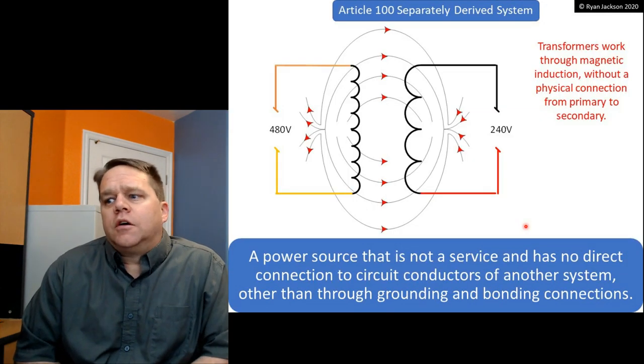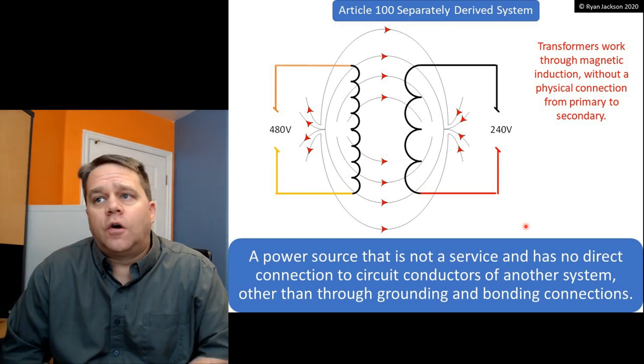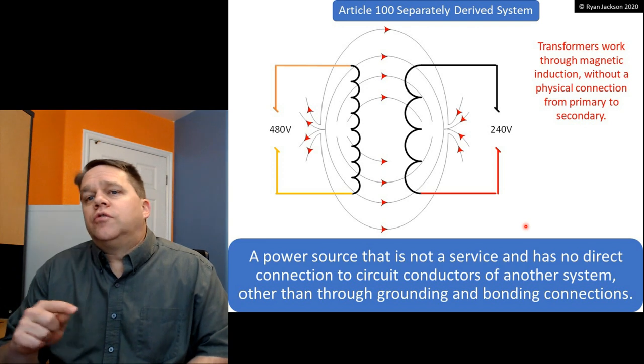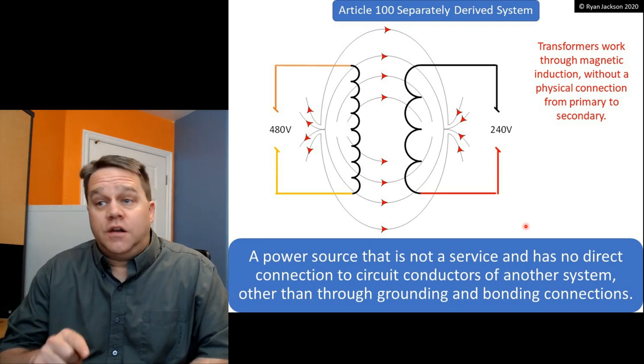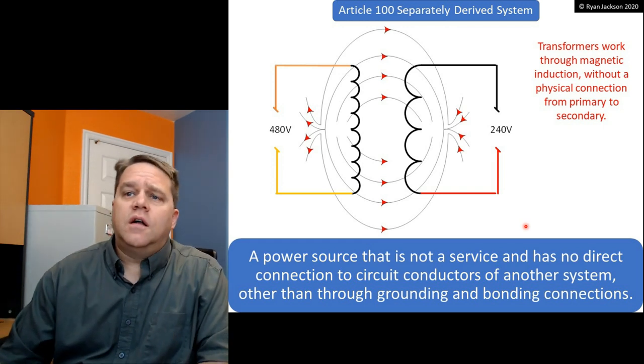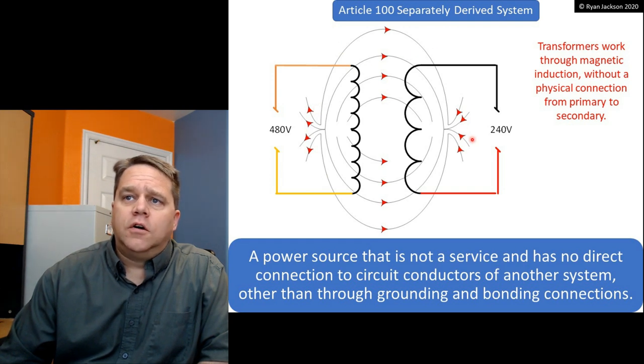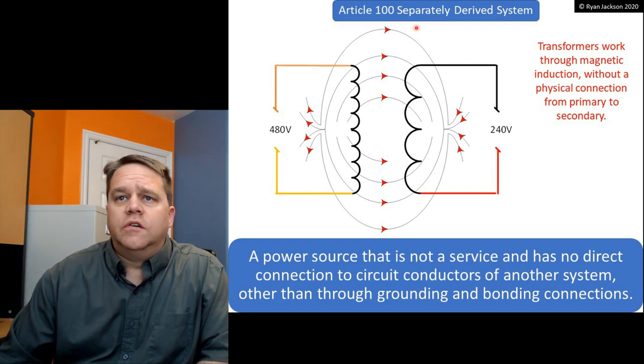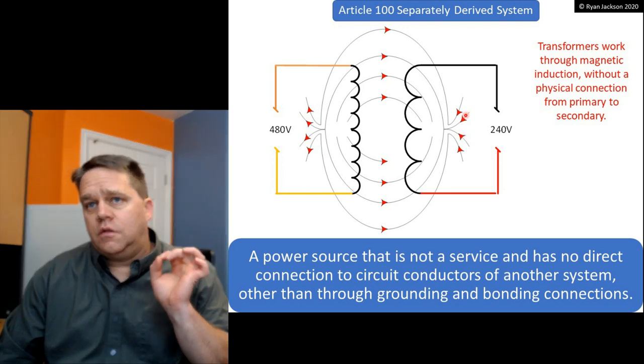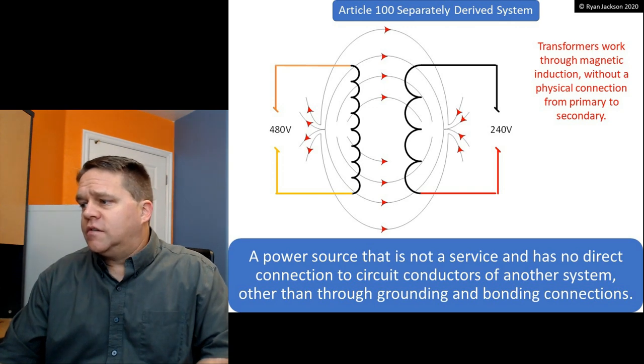A closer definition comes from Article 100 — the definition of a separately derived system. That is a power source that is not a service (so it's not a utility), and it has no direct connection to circuit conductors from another system, other than through grounding and bonding connections or through the earth itself. The concept here is magnetic induction. On the left we have the primary, on the right the secondary. We energize a coil of wire on the left, and that induces a voltage and current on the coil on the right — no direct electrical connection. So it is a separately derived system.